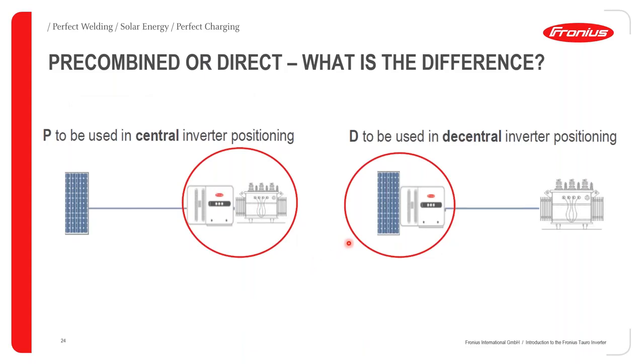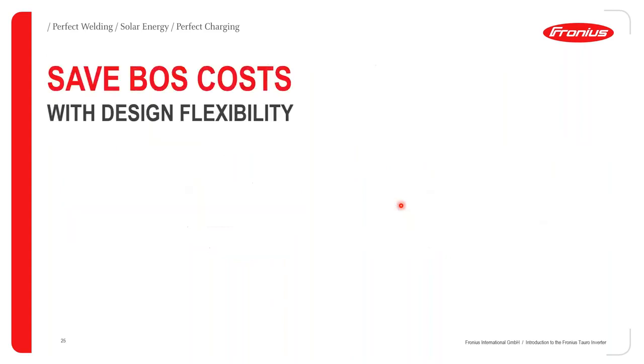In the pre-combined version, we are talking about an inverter that is positioned quite a distance from your PV array, and therefore you are coming with either 2 big cables from the PV array into the inverter DC area. Then looking at the direct version, or what you call the decentralized design, the inverter is getting fed directly from the PV array strings. So the strings are connected directly using MC4 plugs into the inverter.